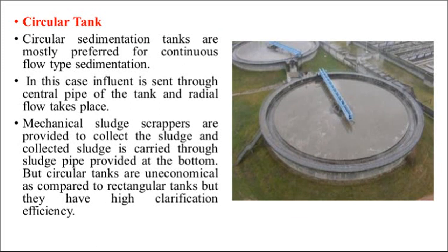The next type is the circular sedimentation tank. Circular sedimentation tanks are mostly used for continuous flow type of sedimentation. The incoming wastewater is sent through a central pipe of the tank and it flows radially. Mechanical sludge scrapers are provided to collect the sludge, and the collected sludge is carried through a sludge pipe provided at the bottom of the tank. Circular tanks are uneconomical compared to rectangular tanks, but they have higher clarification efficiency.